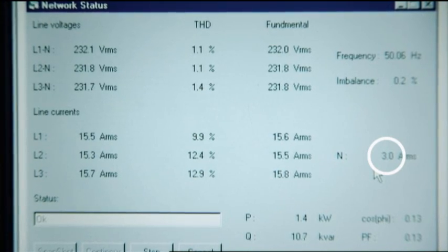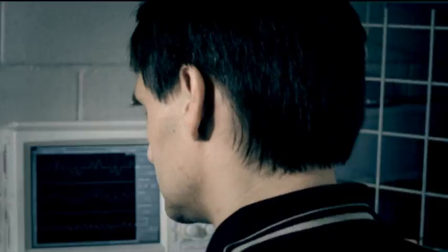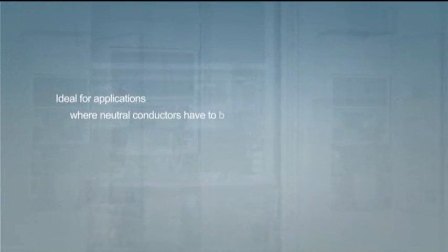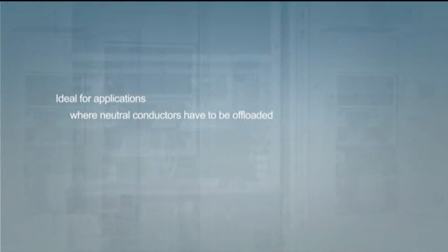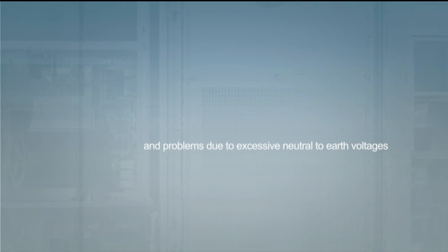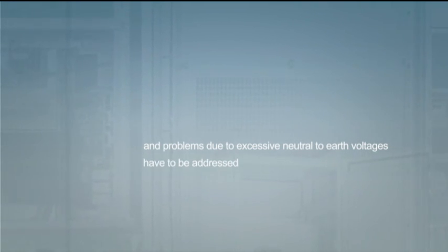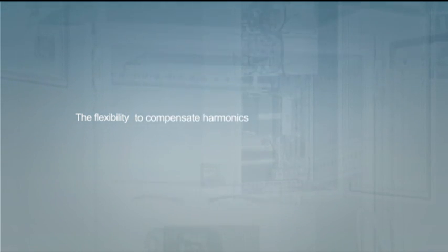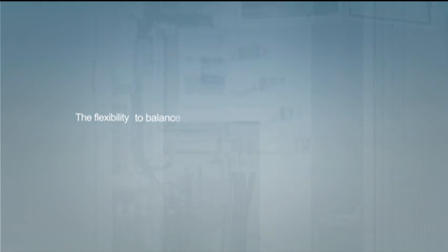This feature of the ABB 4-wire active filters makes them ideal for applications where neutral conductors have to be offloaded and problems due to excessive neutral-to-earth voltages have to be addressed. These demonstrations clearly illustrate the flexibility of the ABB active filters to compensate harmonics, perform reactive power compensation and balance loads.